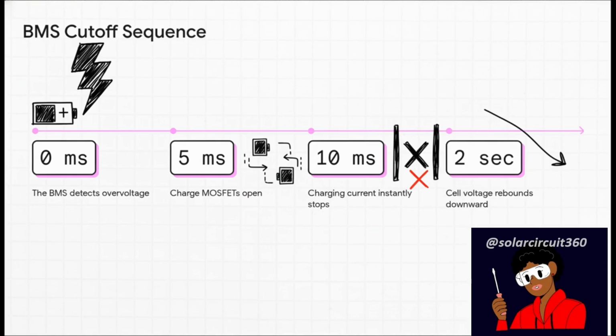In just a fraction of a single second, the sequence is wildly dramatic. At 0 milliseconds, the BMS detects an overvoltage condition. In just 5 milliseconds, it physically opens the charge MOSFETs. By 10 milliseconds, the charging current collapses completely and instantly, entirely severing the charger from the battery pack. Then, maybe a couple of seconds later, the cell voltage actually rebounds downward. It's a violent electrical disconnect under active charging pressure, basically slamming a heavy door shut on massive incoming current.